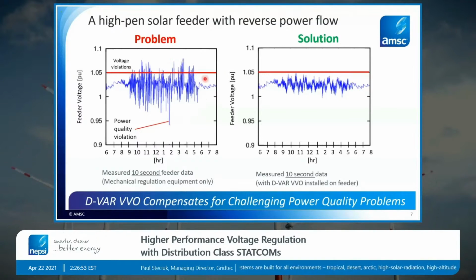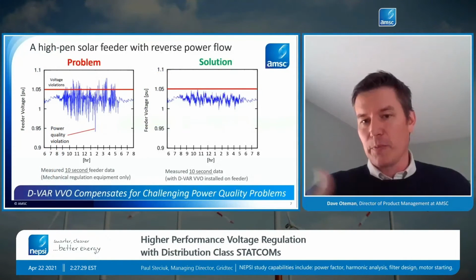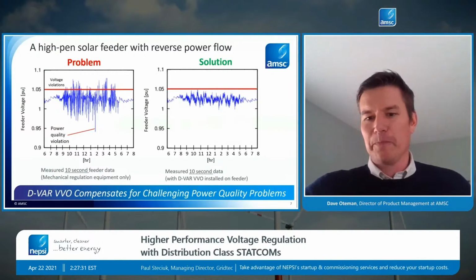A very, very real problem when it's gone unmitigated. This data was taken about 7.5, 8 miles down a radial feeder. On the right is the same feeder, a different day but basically a partly cloudy day with the same problem, after running the STATCOM at near that very same location. Just adding a STATCOM alone, with no other changes to the circuit, the existing mechanical equipment and settings didn't have to change. You just put in a STATCOM and walk away from the problem, and this completely addressed all those power quality issues.